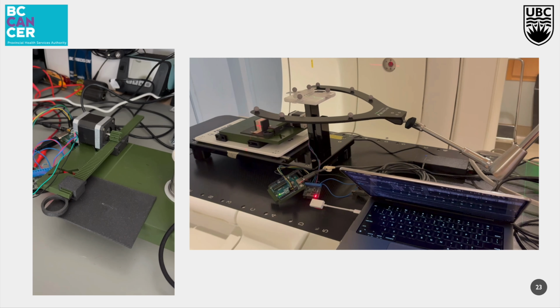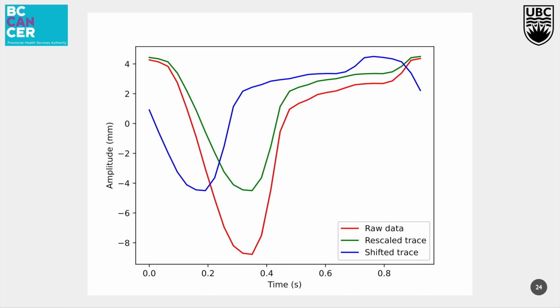And we did some testing to ensure that the cardiac phantom would reproduce the motion expected without any issues. Now, for the actual experiment, I used a single cardiac trace obtained from patient cardiac lead position data, which you can see here in red.